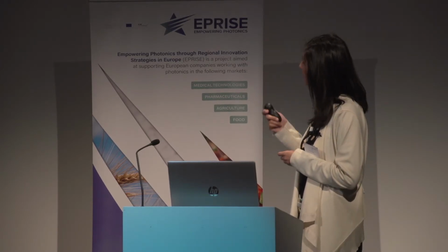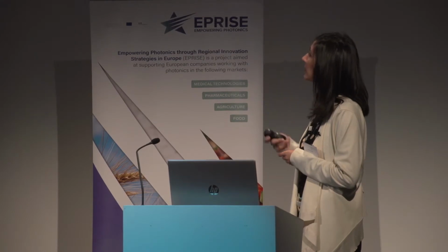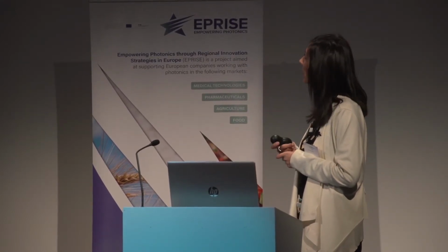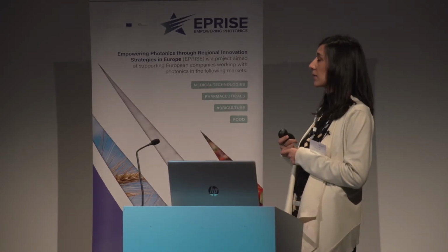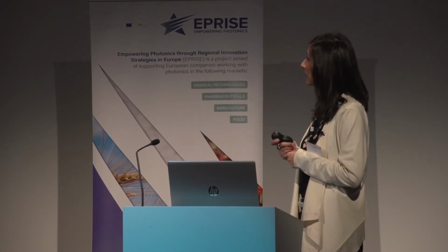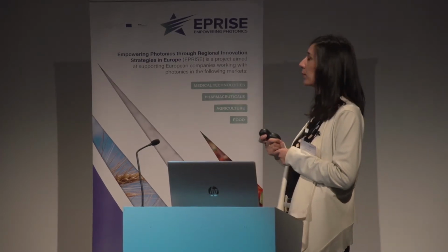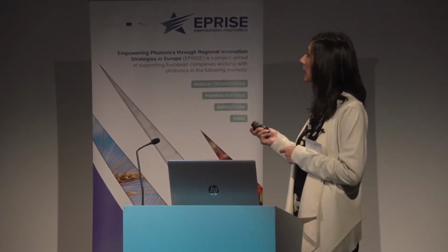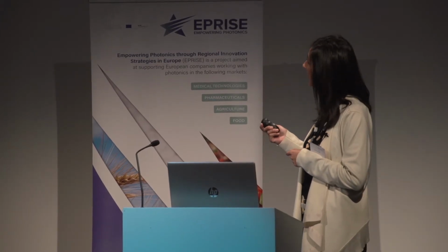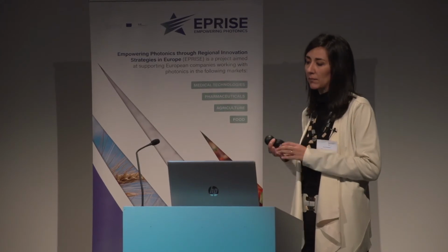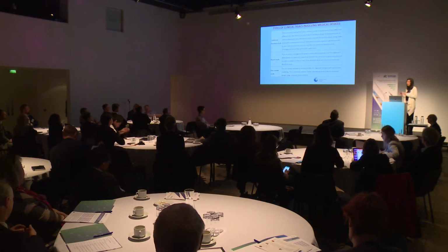And so we have the early feasibility study, in which the study is performed typically before the device design has been finalized. The first-in-human study, in which the study of a device for a specific indication is evaluated for the first time in human subjects. The traditional feasibility study, which is commonly used to capture the preliminary information about safety and effectiveness of the device.